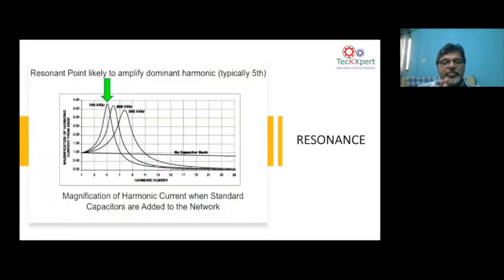Go to the next. Now this is again, as I showed you in the previous slide, as you increase the kVAr on the transformer, you can see the resonant point is getting shifted closer and closer to the low frequency. For 300 kVAr, the resonant frequency is somewhere between 7 and 9. The same system, if you take 500 kVAr on the same transformer, the resonance is shifted between 5 and 7, and if you replace it with 700 kVAr, then the resonance is shifted towards the 5th. That means as you increase the size of the capacitor on a transformer, you are shifting the point of resonance closer and closer to 3 or 5 or 7.